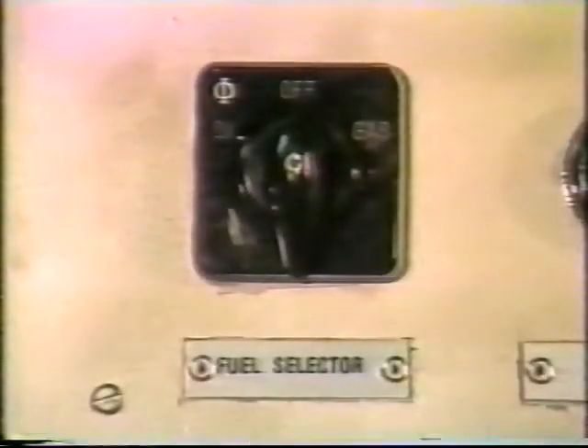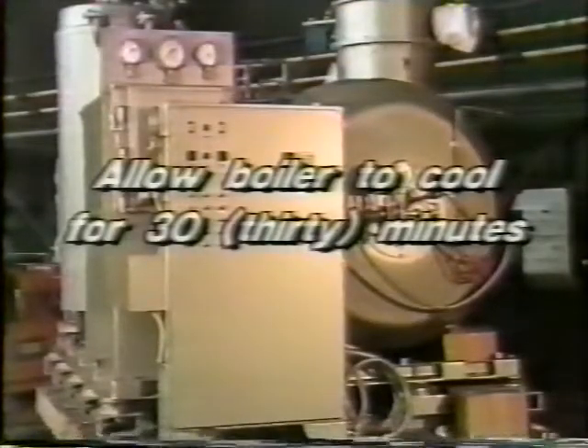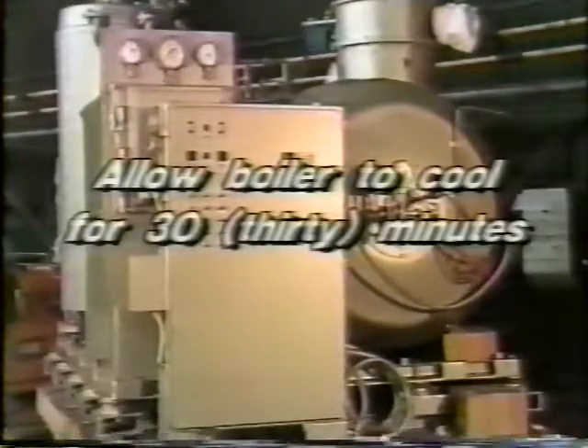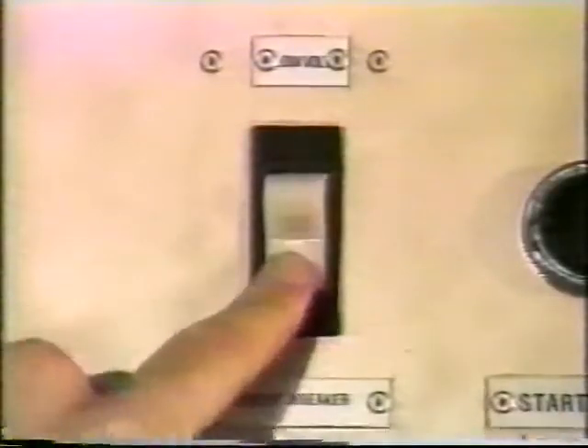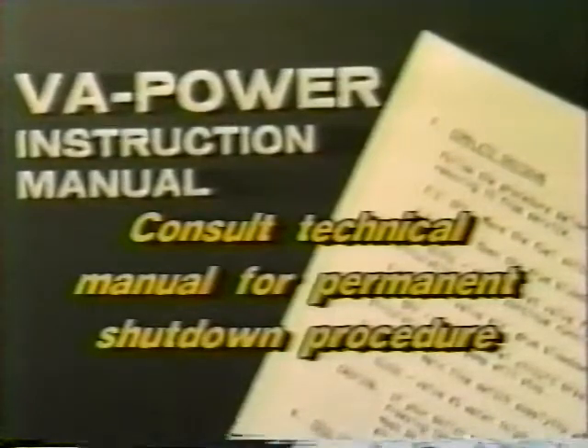Shut down. To shut down the boiler for a short period of time, the fuel switch is placed in the off position. The operator should allow the drive motor to run at least 30 minutes to cool the boiler down. Next, the panel circuit breaker is set to off to stop the circ pump motor. The boiler is now shut down. A time delay relay keeps the blower and water circulating pumps energized after the boiler has been cycled off. Consult the technical manual for the procedure for permanent shutdown and for other details concerning boiler operation.